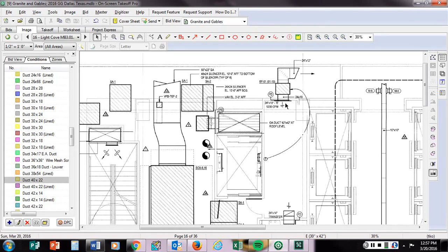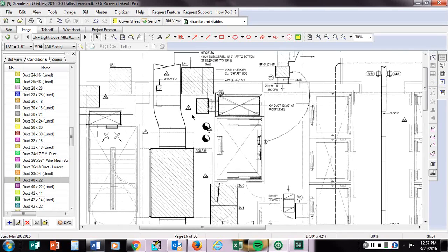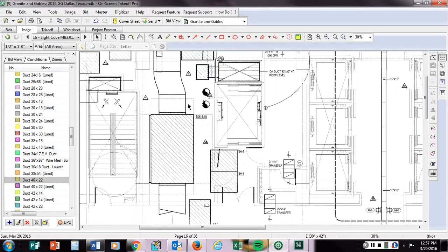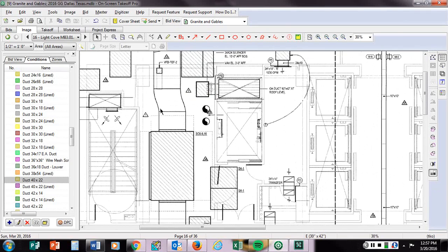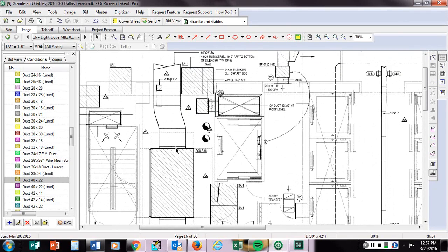That fan sucks the air out of there, goes through an E register, 24 by 10, and blows it into the area outside the room. It gets caught back to the unit, goes through the duct silencer, the transfer duct, and ends up in the mechanical room. In here we've also got a unit and some ductwork. It calls for the first 20 feet of this ductwork to be lined, so we'll say that any of the ductwork up to where it splits off is the only duct we're going to have lined, and I'll show you that on another print shortly.